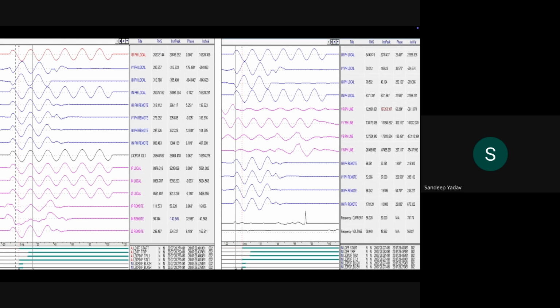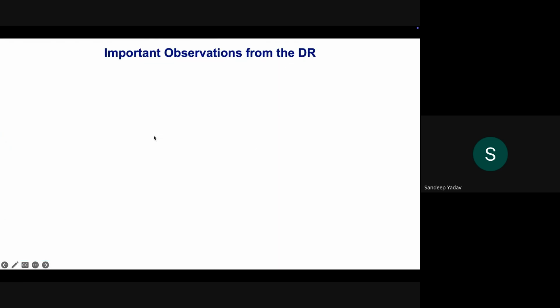Now, I know it will be difficult to read on a PowerPoint on a virtual meeting, but let me guide you through this. The current contributions. This is from the grid side. So again, 26 kiloamperes in the faulty phase, which is R phase, and if you take the remote currents, it is again 300 amps, 318, 278, and 297.